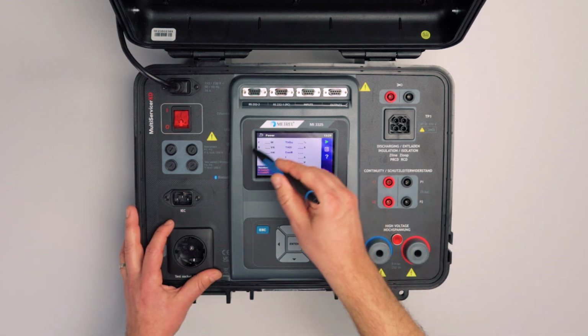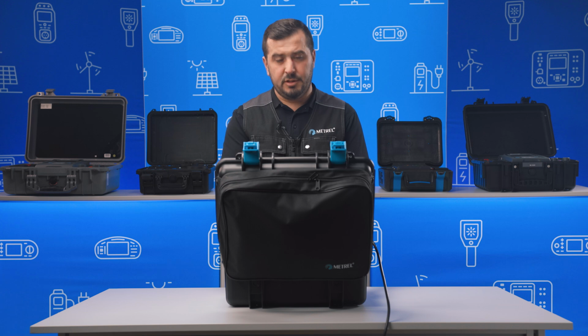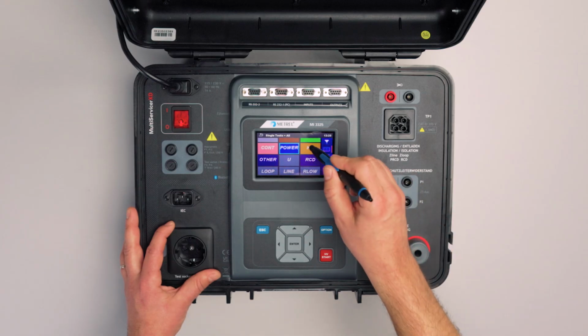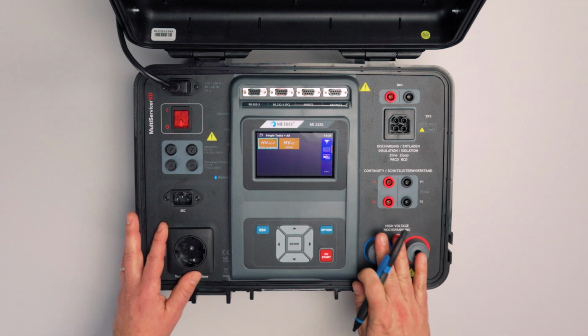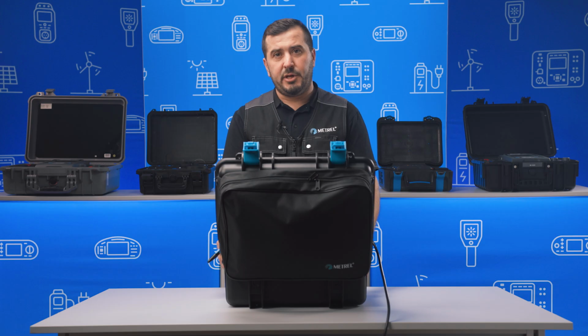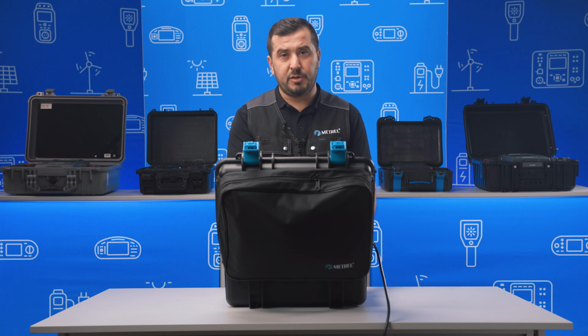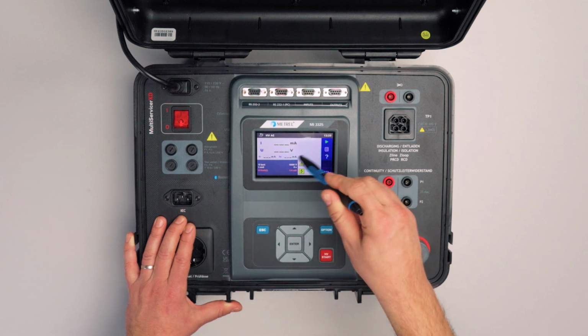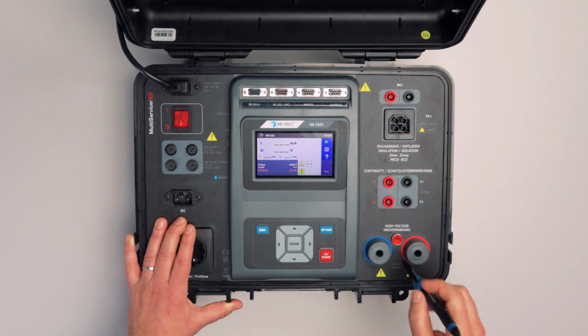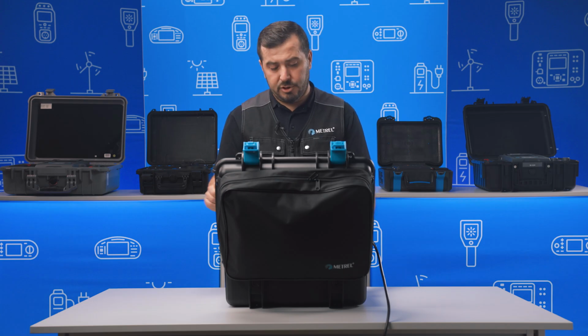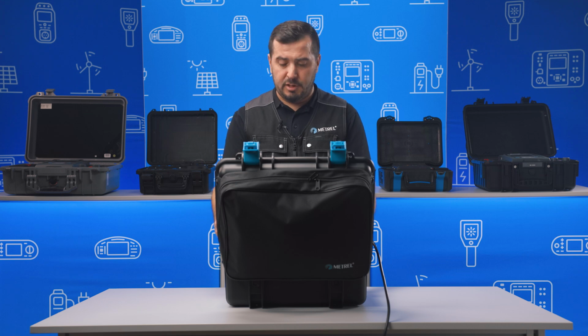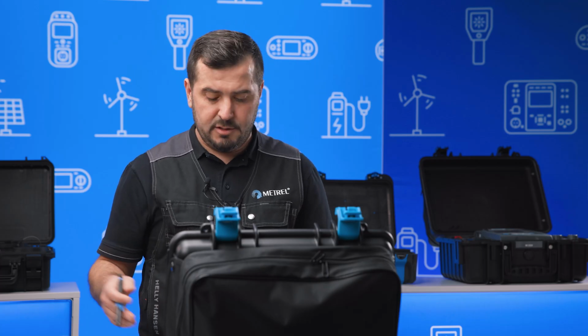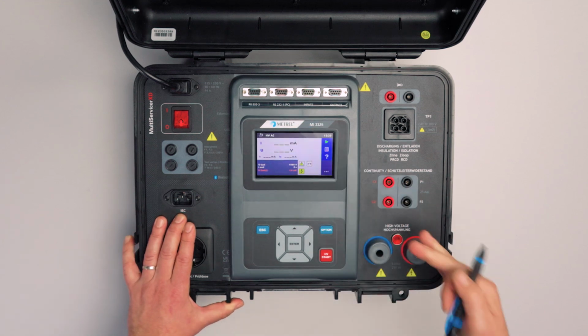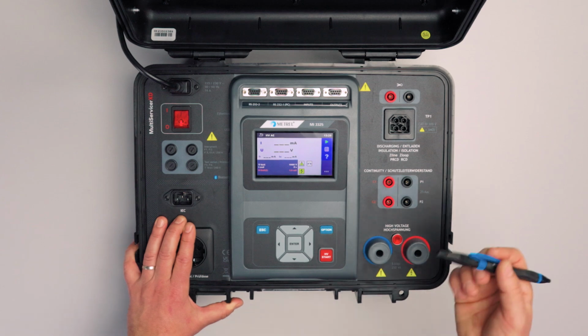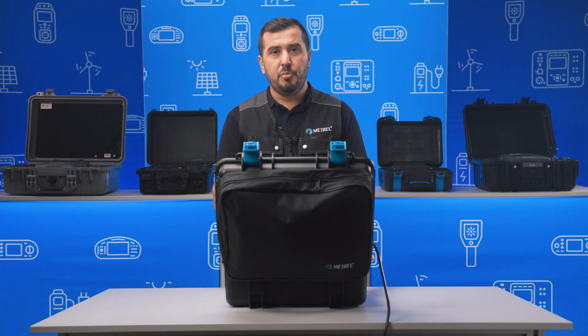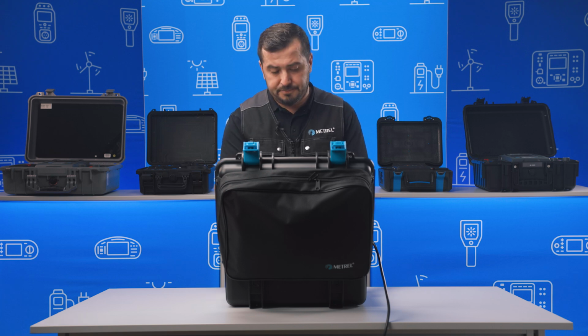Power test, this is the typical power function with all the needed parameters. Then we have the high voltage option. This is for execution of high voltage tests. Two test methods are available, let's say the normal one and the programmable one. If using the normal or simple one, we can simply adjust the test voltage and the duration, and the instrument will apply the test voltage according to the standard to these two test terminals. Of course the measurement will last at least as long until there is any break in the insulation or until the timer is finished.